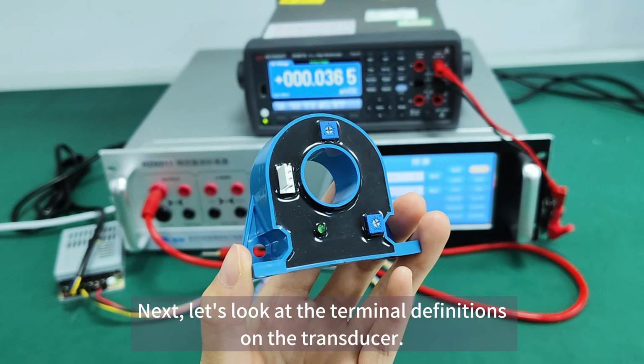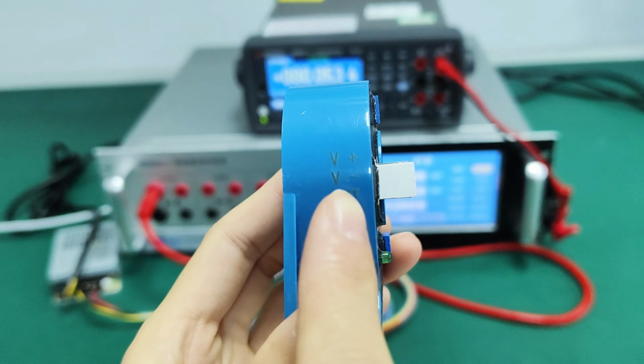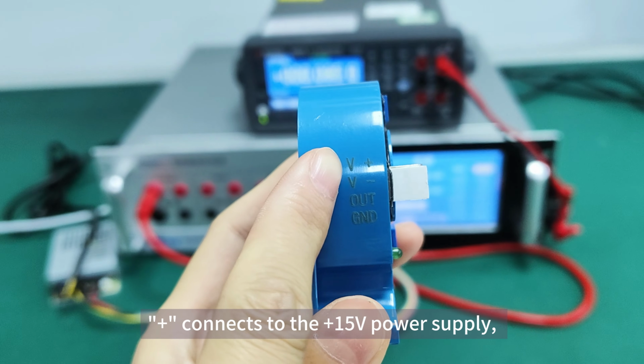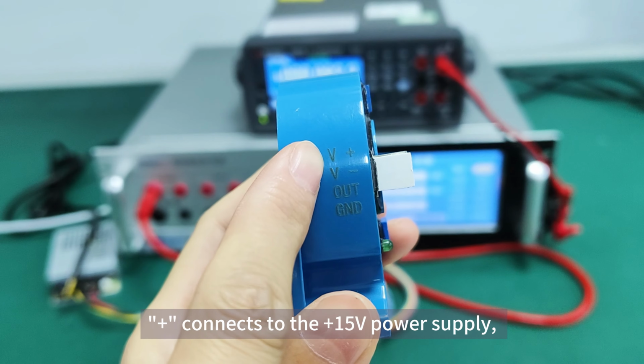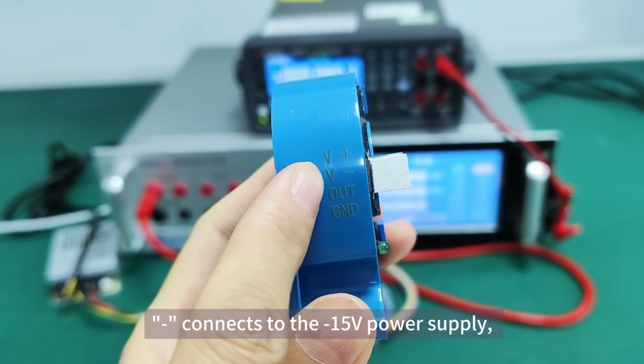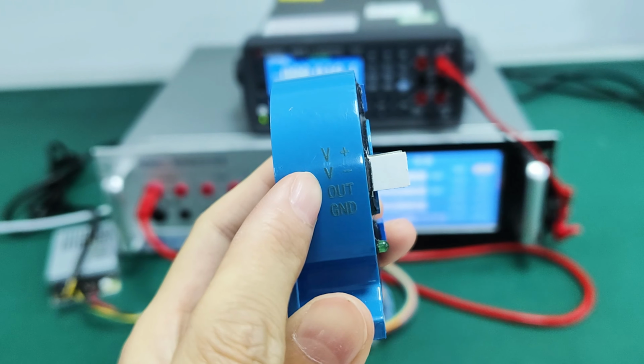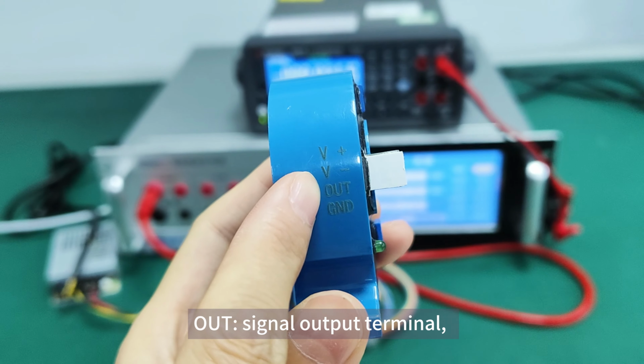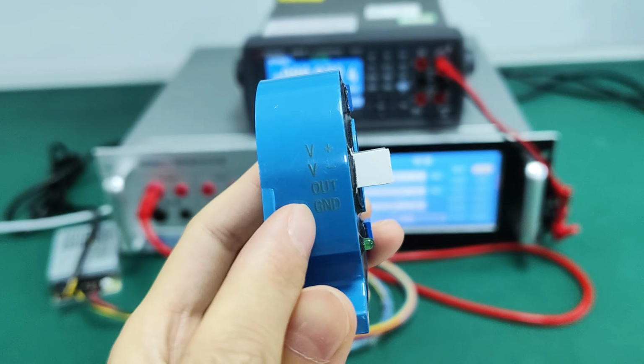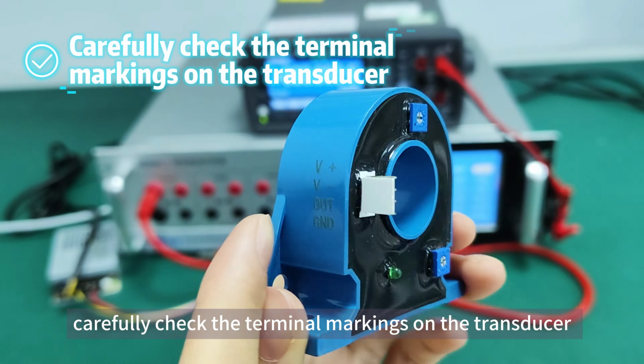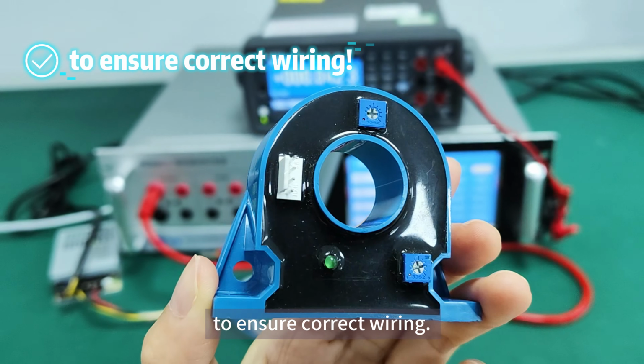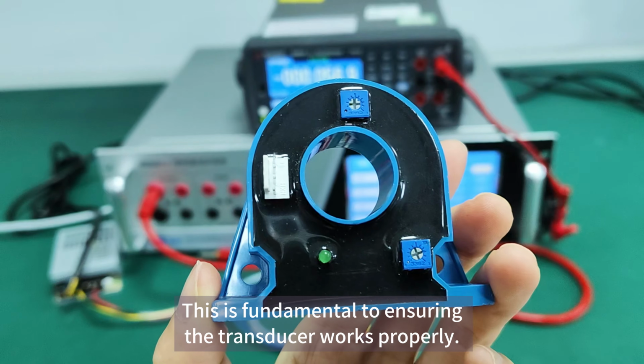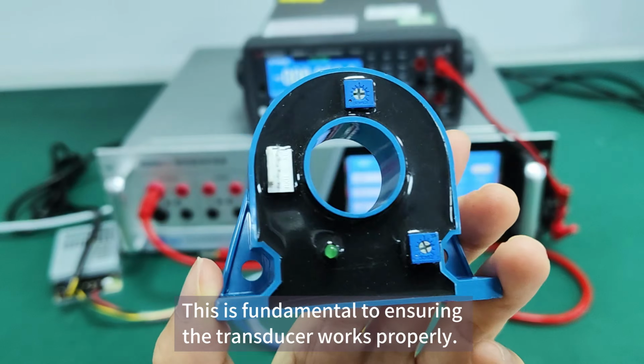Next, let's look at the terminal definitions. On the transducer, from top to bottom, plus connects to the 15 volt power supply. Minus connects to the minus 15 volt power supply. Out is the signal output terminal. GND is the power ground, which is also the common signal output terminal. When wiring, carefully check the terminal markings on the transducer to ensure correct wiring. This is fundamental to ensuring the transducer works properly.